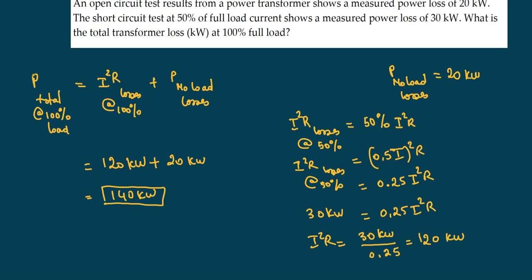This formula is definitely something you need to know — put it in your notebook. If given 75% or 25% or 50%, multiply by the square of that percentage to find the I²R losses. It's really important to understand that the base value is the actual full load losses, so any percentage can be applied to find losses at that load level. Let me know if you have any questions in the comments below.